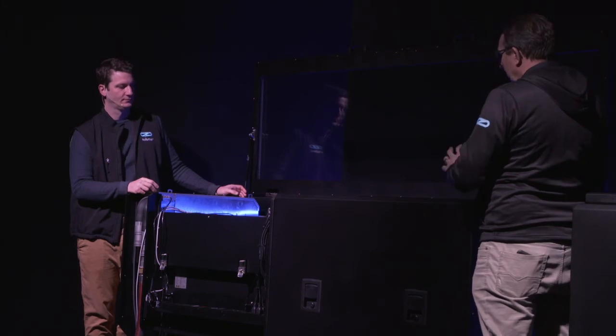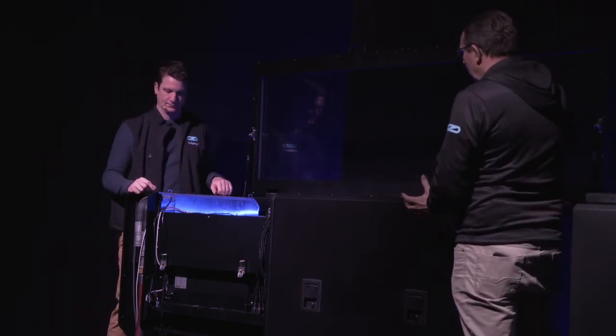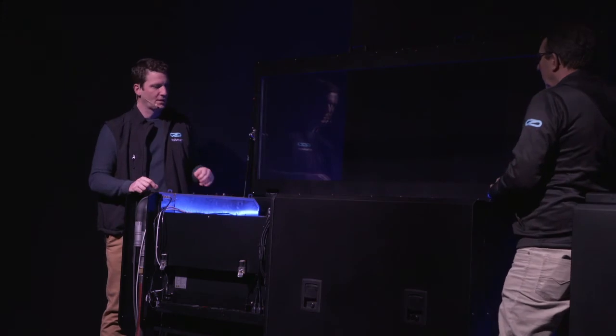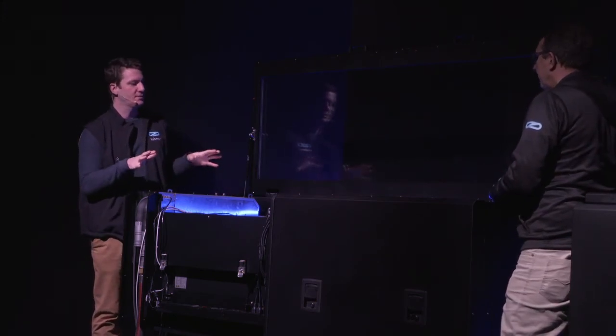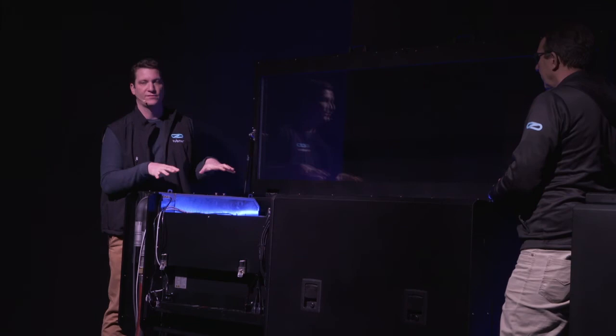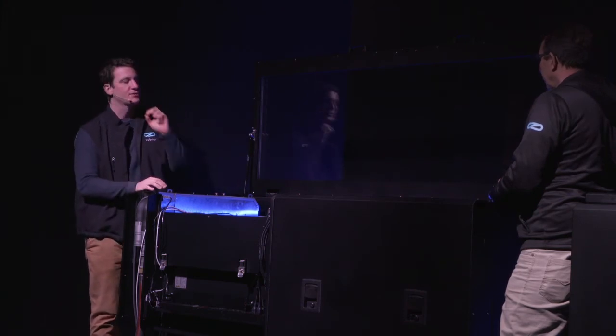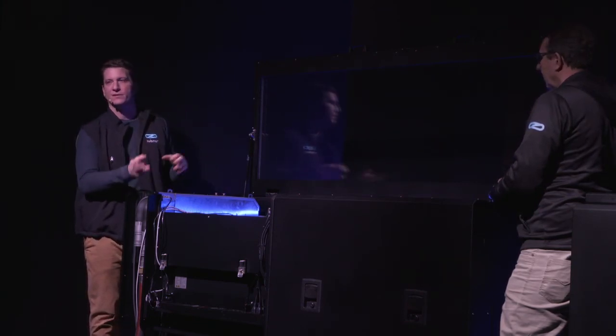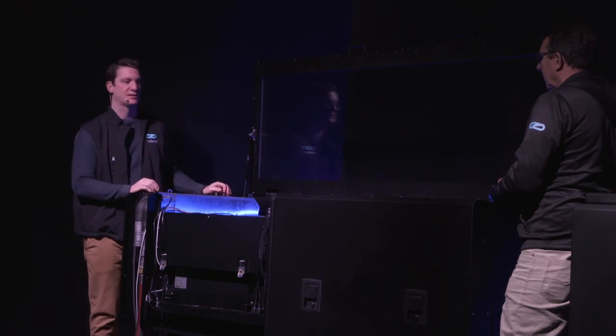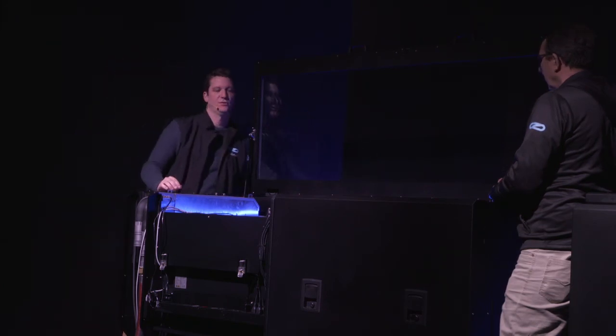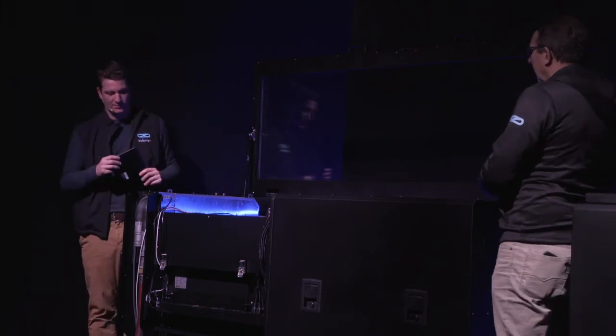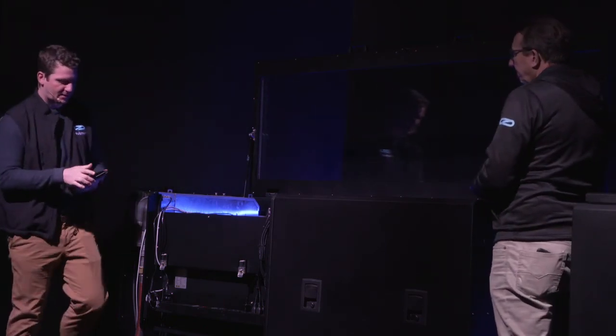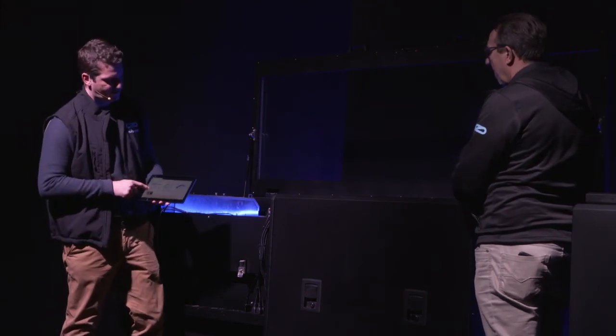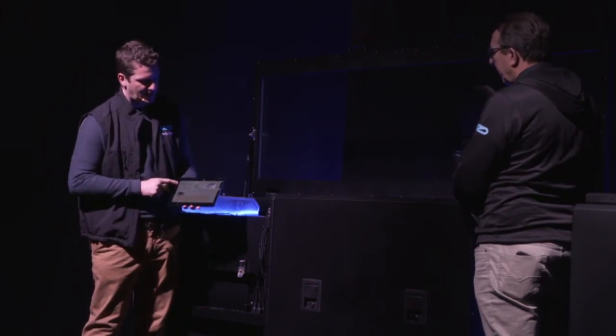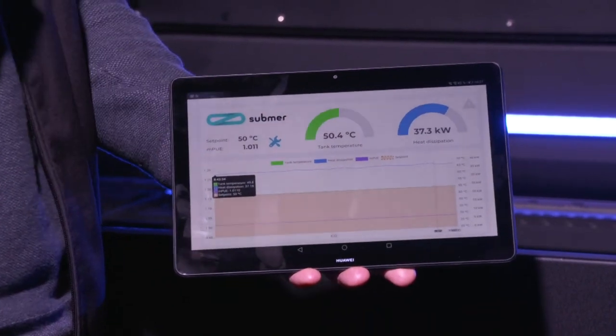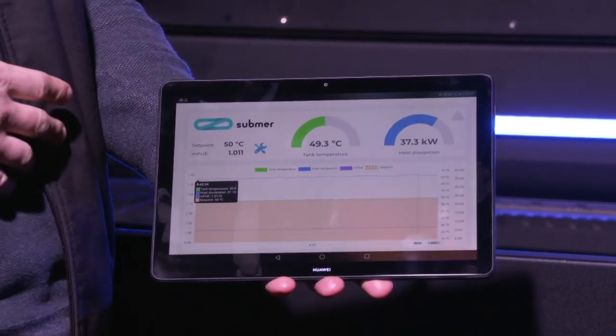Absolutely. Now, we've talked about the liquid, we talked about the dry zone. What can you tell us about the telemetry? Yeah, so these systems have more than 25 sensors in them. Those sensors monitor everything from temperature, flow rates, the heat that's being exchanged, fluid quality, etc. And all that telemetry is accessible through an open API. At the same time, we obviously represent that on a visual interface to allow customers to, in this case, see the operation of a single unit.